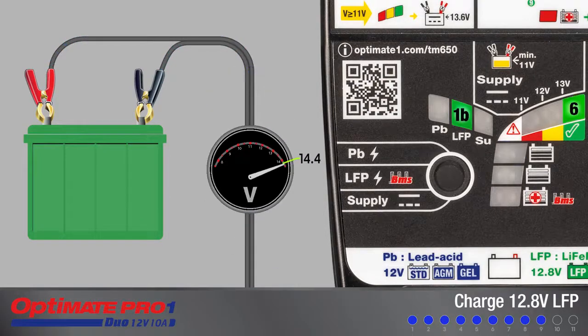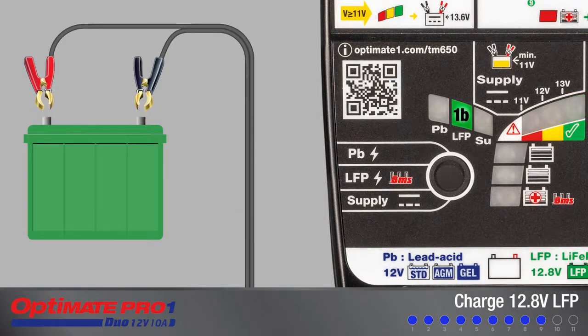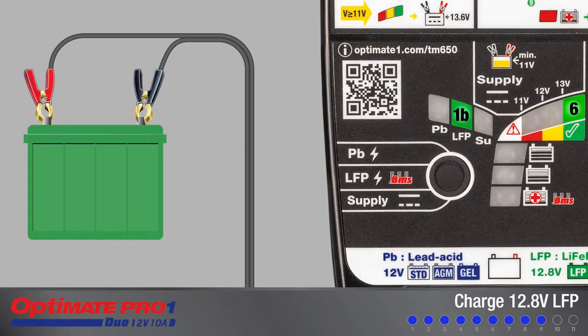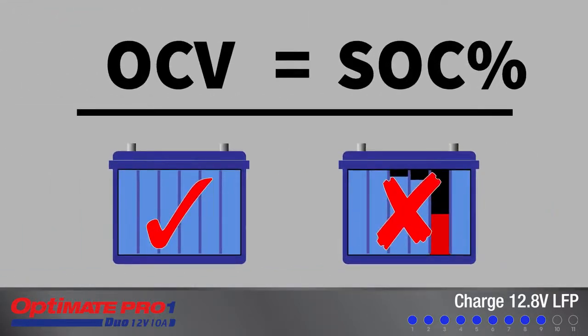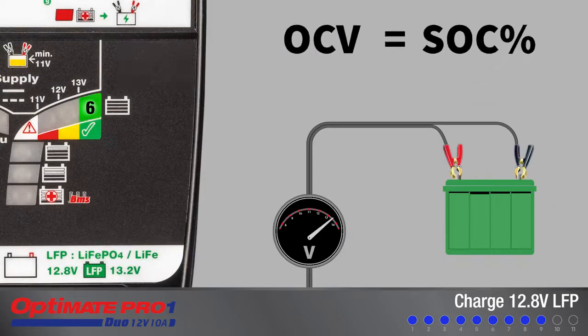Now charging has been completed for new batteries, and the new battery is ready for use, but it can be left connected. A used battery should be left connected so that the program can complete a state of charge test. This test determines the serviceability of the battery. The open circuit voltage of a battery is directly proportional to its state of charge percentage after it has been allowed to settle for 30 minutes or more.